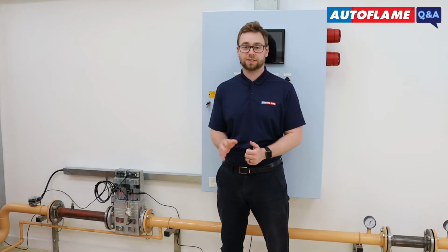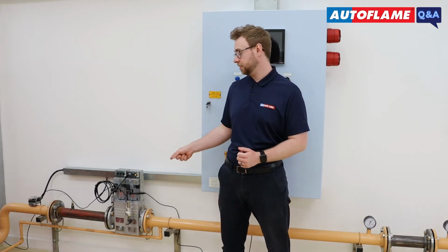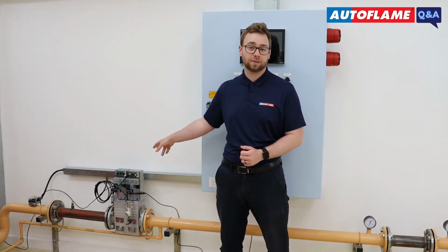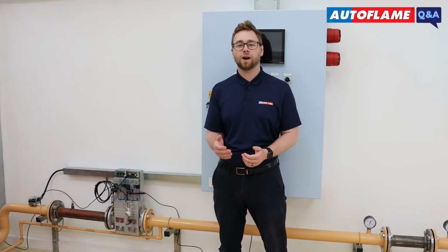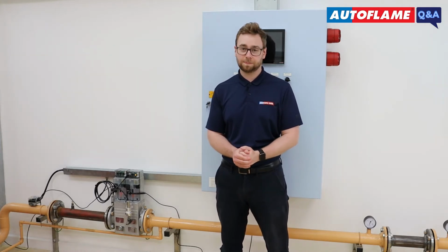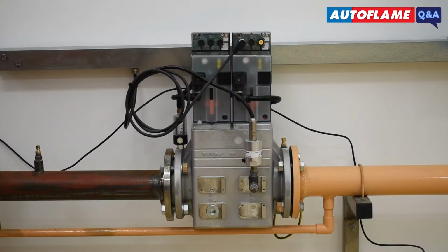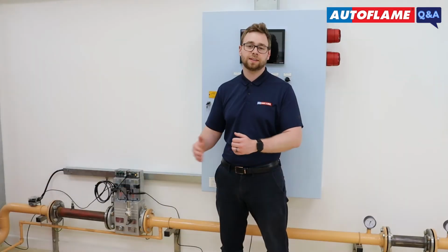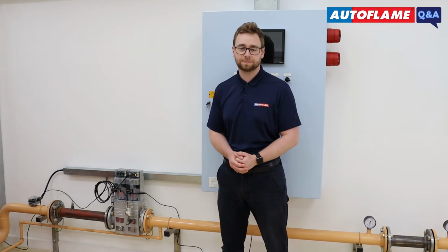When configured for gas valve proving, or VPS, the gas pressure sensor will monitor your gas pressure continuously as the controller energizes and de-energizes your two main gas valves and your vent valve if you have one, ultimately testing for valve integrity. You can see here we've got the gas pressure sensor mounted vertically in between the upstream and downstream main gas valves. In this case, we're using a Dungs double block valve assembly.